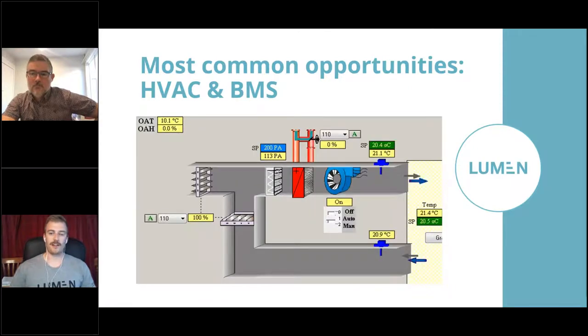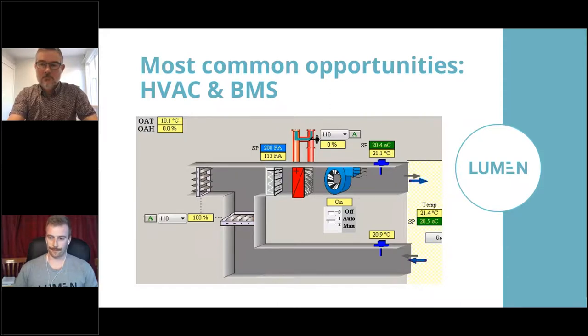So this is an air handling unit for one of our clients where I managed to find the trifecta. You can't tell from the image, but this was operating during the middle of the night and no one was there. So that was number one. If you look at the outside air temperature, OAT, it's bringing in 10 degree outside air, 100% outside air. It's passing over a coil that's supposed to be shut at 0%, and it's heating up to 21 degrees. So not only are we bringing in 100% outside air for no one in the building, we're also heating it up and wasting a lot of energy that way.